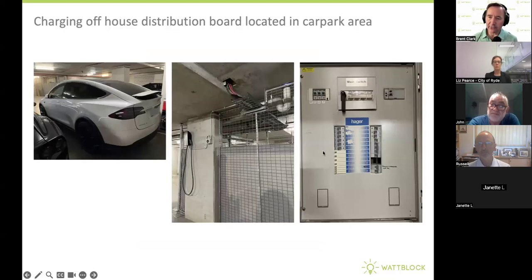This is an example of a house distribution board installed into different levels of the basement car park for the purpose of charging an electric vehicle, running via cable tray from this house distribution board. One of the things to really protect your apartment building in the best way from EV charging fires is to have dedicated distribution boards connected to the house power for charging electric vehicles, with kill switches connected to the fire control panel. So if there's a fire for any reason in the building from any source, a message is sent to stop all EV charging immediately in the basement car park, regardless of the source of the fire. That can be done through having dedicated EV charging distribution boards in the car park area.